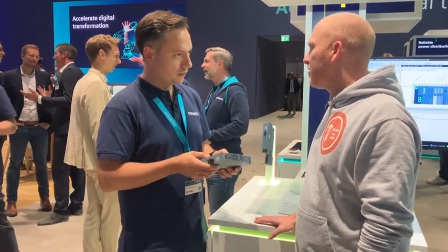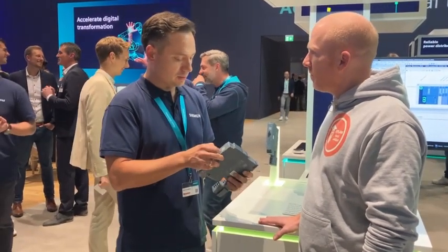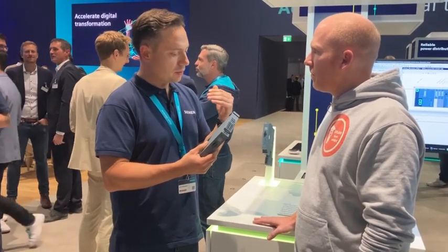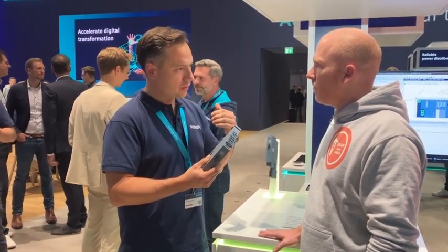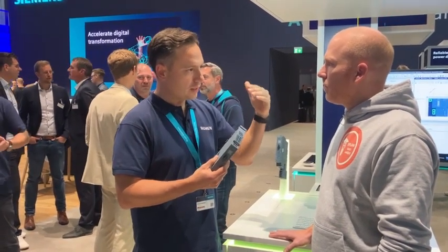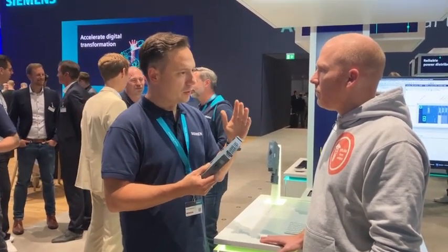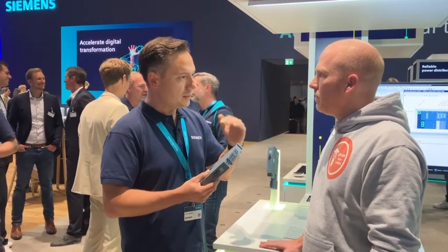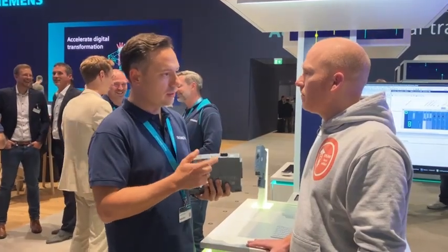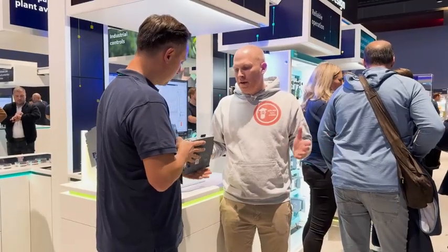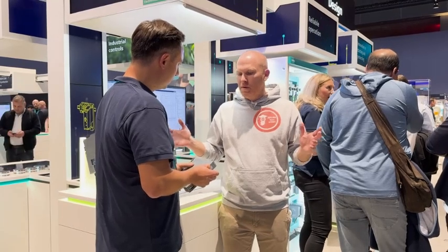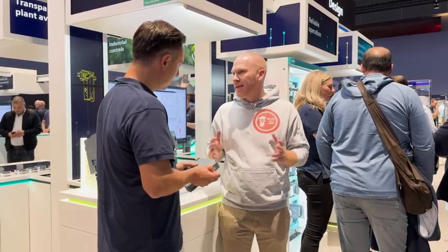This is really fast. The biggest advantage is, you have to imagine, with this speed we avoid that the short circuit current goes up into the kiloamp range. We are at about 150, 160 amps, and that's it. So we don't have any destructive short circuit current anymore. But anyhow, it just trips when the short circuit happens. What is the big advantage of this fast tripping?